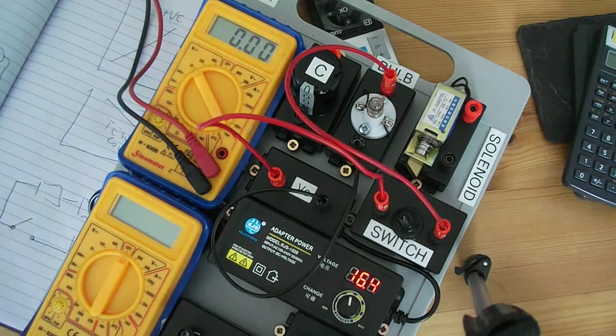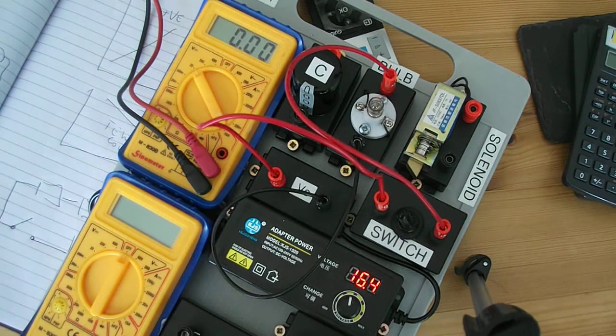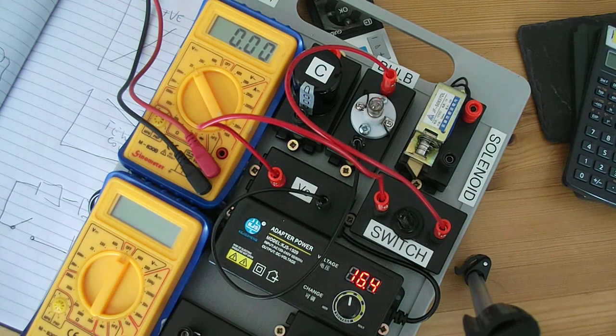Which proves that particularly at high voltage, if a switch is off and the supply is off, if you went to work on that switch, it doesn't mean it's safe. It's not isolated because there's still a voltage across the switch.